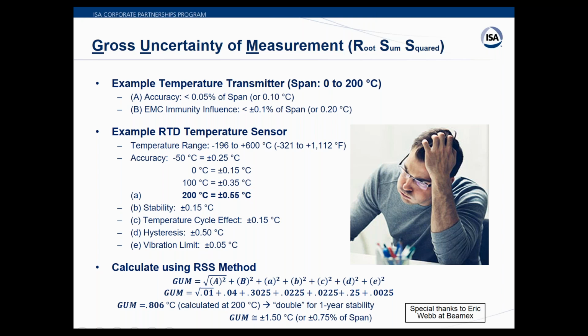Well, no, because that's one component, and that's a good question, Roy. Everybody focuses on the accuracy, but this is twice as big as this. And we don't even look at the EMC immunity influence, but in this case, it's quite significant compared to this guy. The other thing that bothers me on this example is there's no drift, and we all know instruments drift. So, how does this instrument perform in 6 months? How does it perform in 12 months? It's going to be different than 0.05%.